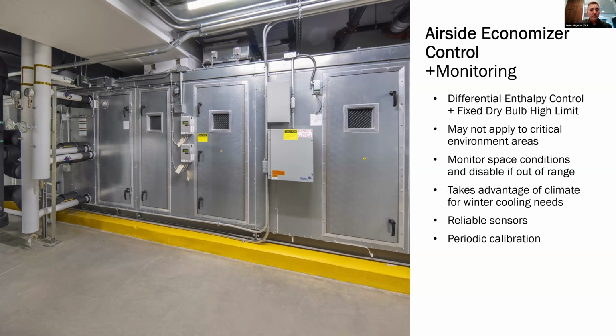I wanted to make a quick point about humidity sensors. In a museum, humidity sensors are critical, not only to a sequence like this, where you're looking at differential enthalpy control and space humidity, but you really want reliable humidity sensors. You've got to make that investment up front on day one, but you also have to make that investment annually, or I would say periodically, based on the manufacturer's requirements for calibration, because they do go out of calibration. So that's something to talk to the facilities team about at the start of a project, and talk about which sensors are right for the museum, because that can be a pretty large investment.